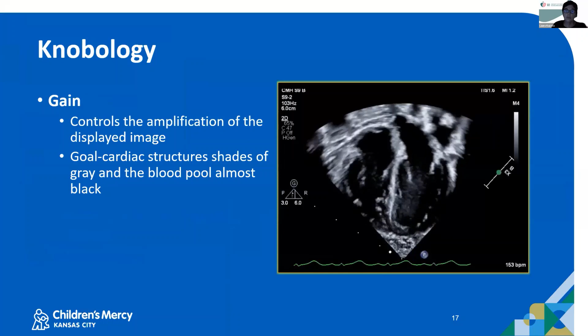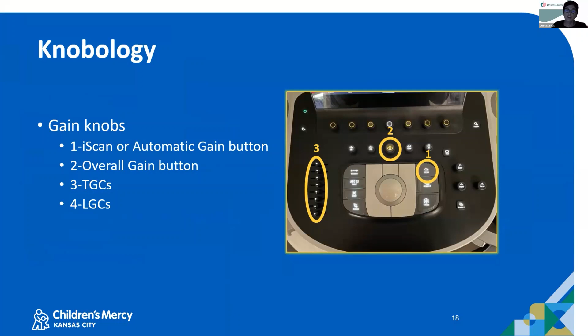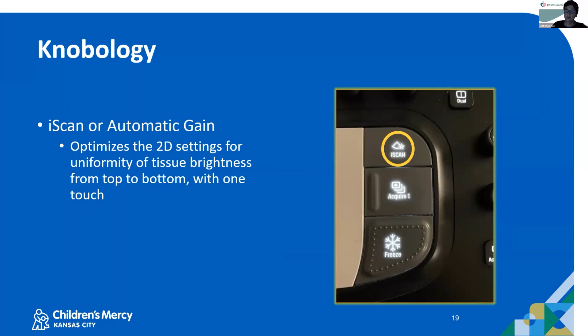There's a few ways to optimize gain. The first thing you can do is your iScan or your automatic gain button, and then you can do your overall gain button. You have TGCs and then you have LGCs. So the iScan or the automatic gain button is just a one-touch button. You hit the button and the machine's going to automatically adjust the brightness and gain from top to bottom to something that should be a fairly good starting point. Sometimes that's all you need to do.